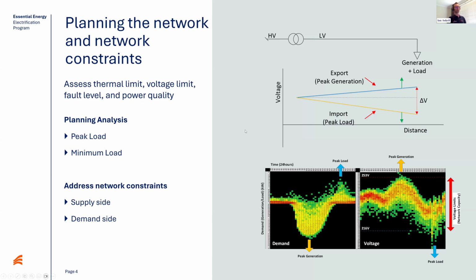On the right-hand side is one of the examples we assess. We look at thermal limits and voltage limits - we must maintain voltage within set limits for supply to customers - and there's also fault level analysis completed to ensure adequate protection coverage.